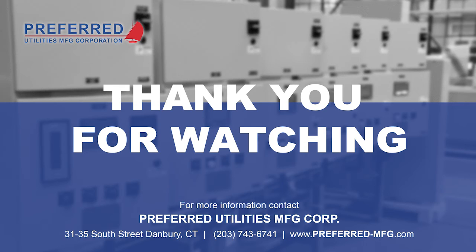When are anti-siphon valves needed versus using a solenoid valve? This question came in before we got to that slide, but just for review purposes, the anti-siphon valve prevents draining a tank through siphonic action if you get a break in the line below the level of stored fuel. And we always prefer to use an anti-siphon valve in that application, but Preferred's anti-siphon valves only go up to 1,100 gallons per hour, and we make pumps.